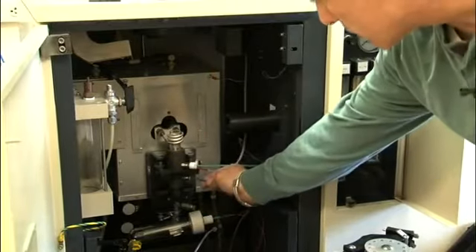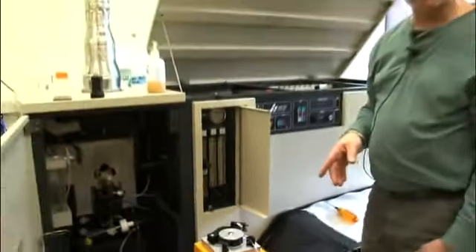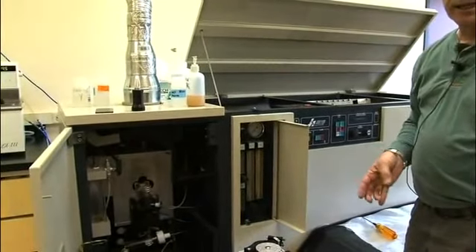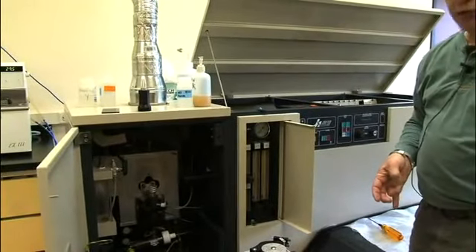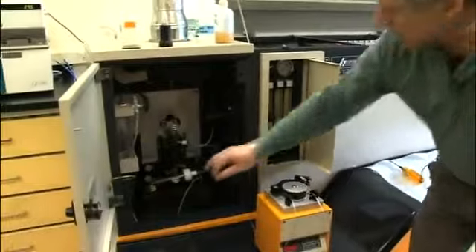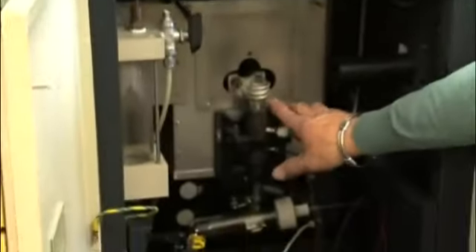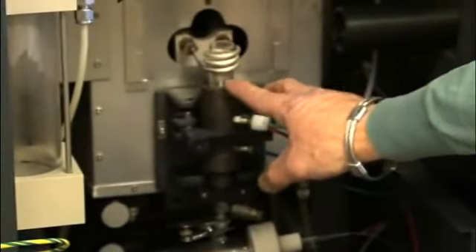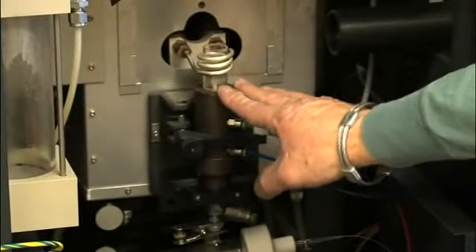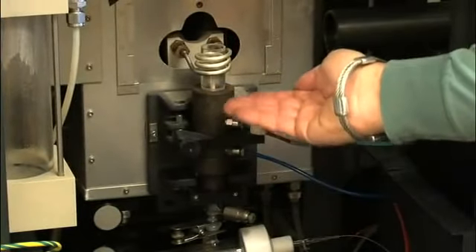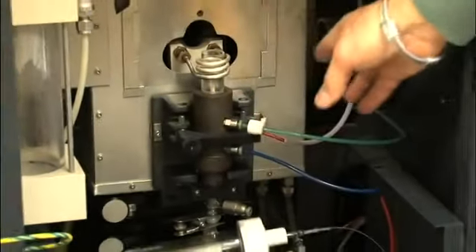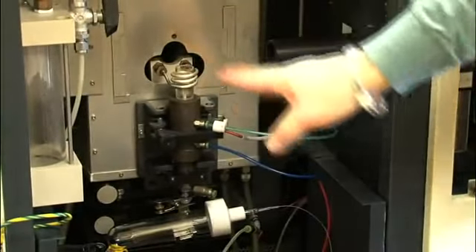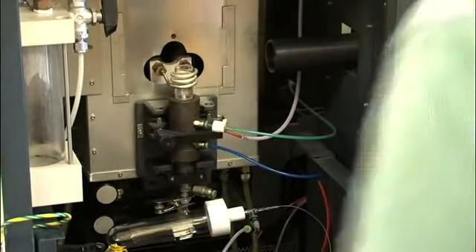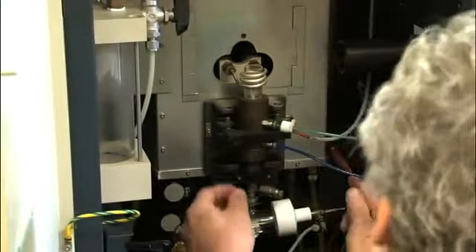Your next one is your auxiliary gas, which is only used when you're running organic samples, xylene or kerosene matrix. What that's going to do is, when you have an organic plasma, the plasma is going to want to sit on top of the inner quartz tube, and the auxiliary just pushes the plasma up. Otherwise, it'll carbon up that whole inner quartz tube. You won't see anything. Your red goes down here.